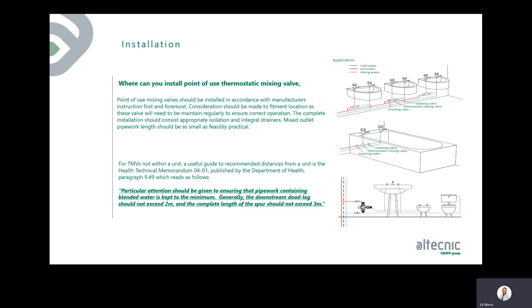For TMVs not within a unit, HTM 04-01 published by the Department of Health provides guidance on recommended distances. Paragraph 9.49 states that particular attention should be given to keeping blended water pipe work to a minimum — the downstream dead leg should not exceed two metres, and the complete length of the spur should not exceed three metres.